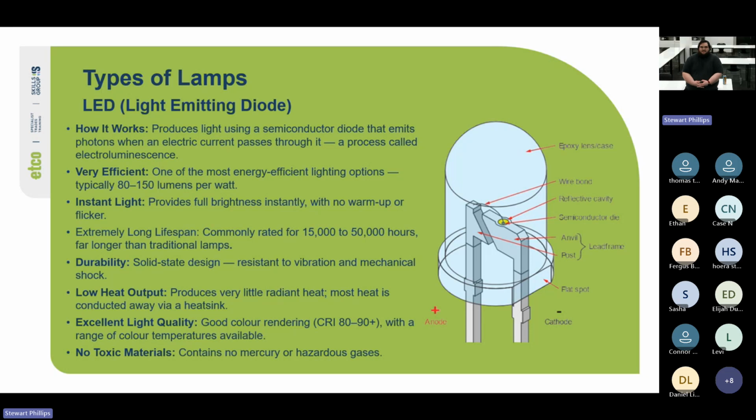I've had more LEDs fail to ant infestation, water ingress, and just being physically damaged than I have to actually failing since I've started doing electrical. So they're quite durable. They've got a solid state design, so they're resistant to vibration and mechanical shock. They put out very little radiant heat. Most of the heat is conducted away and is at the driver.